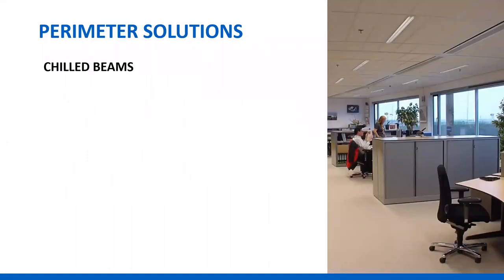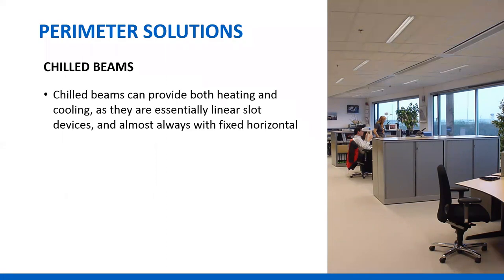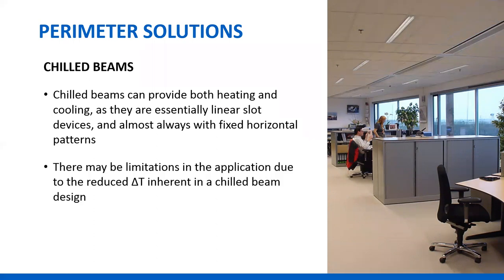Chilled beams have been used at the perimeter — they're best used in a temperate climate. Because a chilled beam is an induction device, the discharge temperature will not be as cold or as hot as the supply air or the coils producing heating or cooling. As a result, there are limitations to how much perimeter load they can actually handle. In a non-temperate climate, you might want to consider baseboard or other solutions in the perimeter zone along with chilled beams. There is inherent limitation due to the reduced delta T in a chilled beam design.